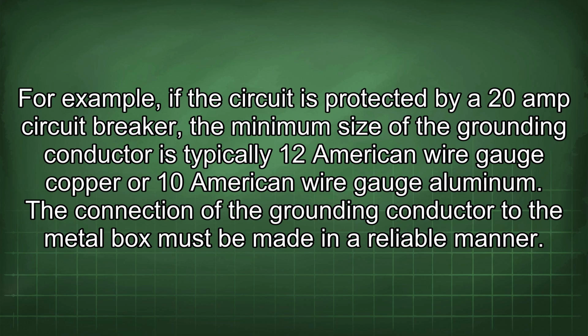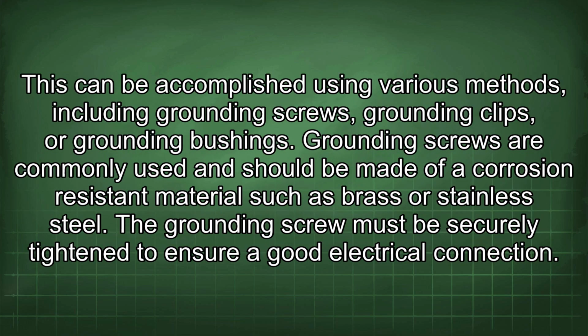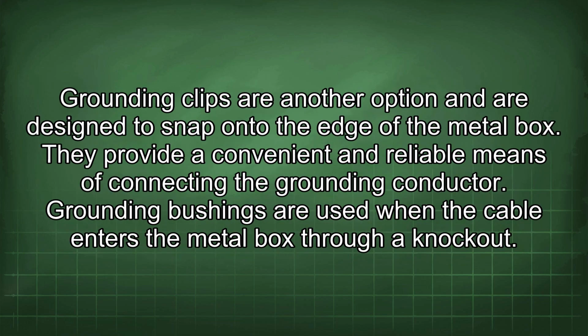The connection of the grounding conductor to the metal box must be made in a reliable manner. This can be accomplished using various methods, including grounding screws, grounding clips, or grounding bushings. Grounding screws are commonly used and should be made of a corrosion-resistant material such as brass or stainless steel. The grounding screw must be securely tightened to ensure a good electrical connection. Grounding clips are another option and are designed to snap onto the edge of the metal box. They provide a convenient and reliable means of connecting the grounding conductor.